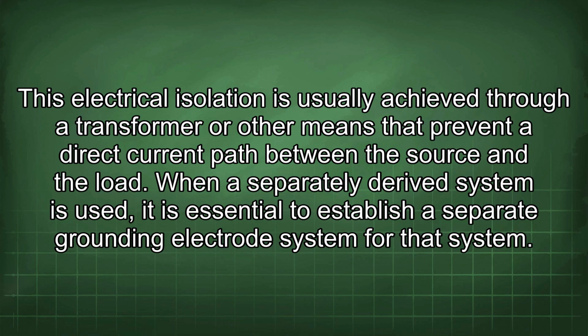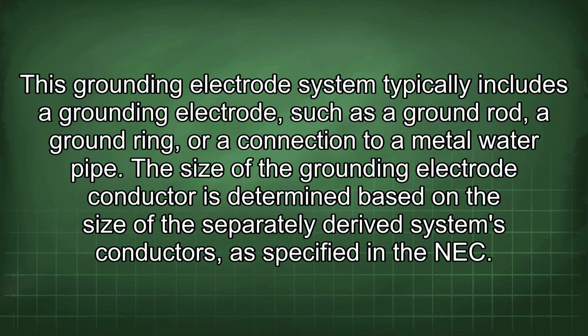This electrical isolation is usually achieved through a transformer or other means that prevent a direct current path between the source and the load. When a separately derived system is used, it is essential to establish a separate grounding electrode system for that system. This grounding electrode system typically includes a grounding electrode, such as a ground rod, a ground ring, or a connection to a metal water pipe.